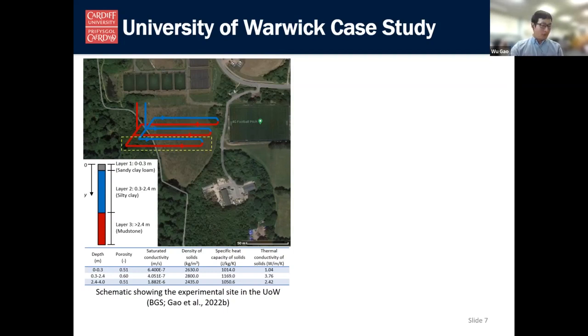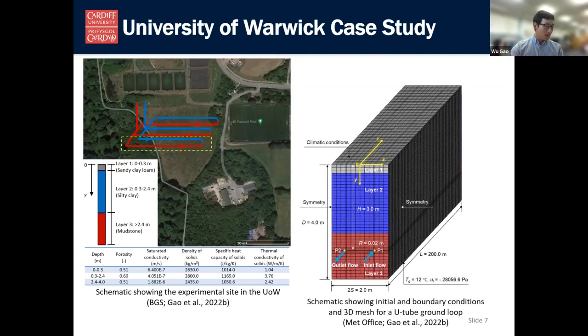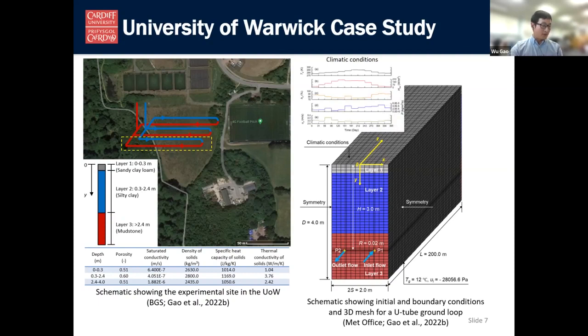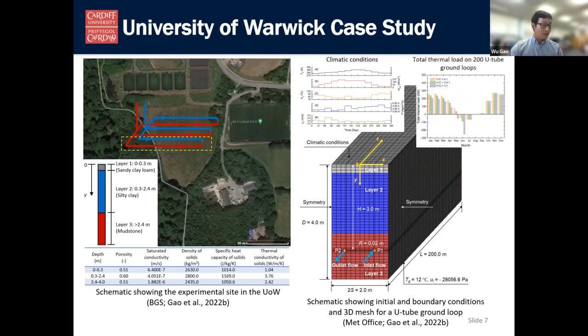Taking one representative unit of the horizontal ground loop as an example, as shown in the right figure, a 3D model domain is built. As shown in the figure, the U-tube ground loop was buried 3 meters below the ground, and the length and spacing of the 2 legs of the ground loop were 200 meters and 1 meter respectively. On the domain surface, local climatic conditions were prescribed, and fixed temperature and saturation were assumed at the bottom of the domain. In addition, the thermal load from 3 buildings of the experiment site was prescribed on the ground loops.